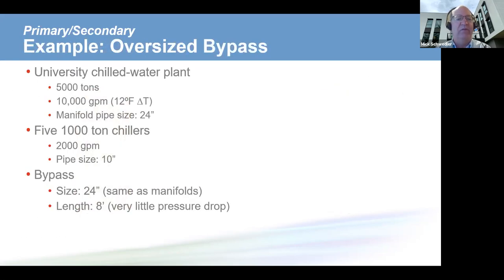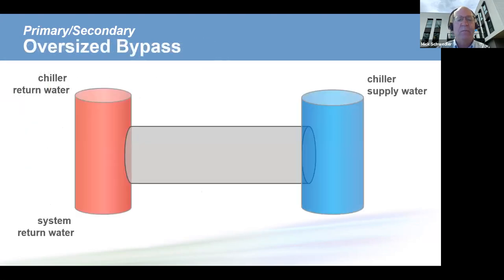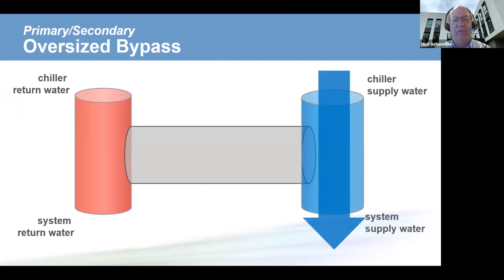So we have an example here, and this is a university plant. It's a large plant, and the bypass size is the same as the manifold. And it's a short bypass line, so we have our chilled water supply pipe, our chilled water return pipe, and the bypass line is only 8 feet long, so there's very little pressure drop. Well, what happens is that we have water that's being produced from our chillers, and it's being sent out to the chilled water system supply in the coils.